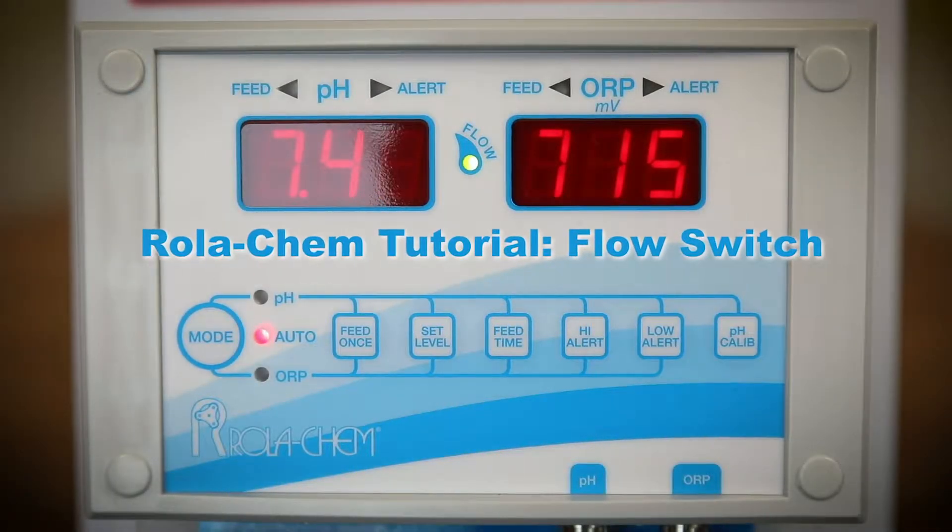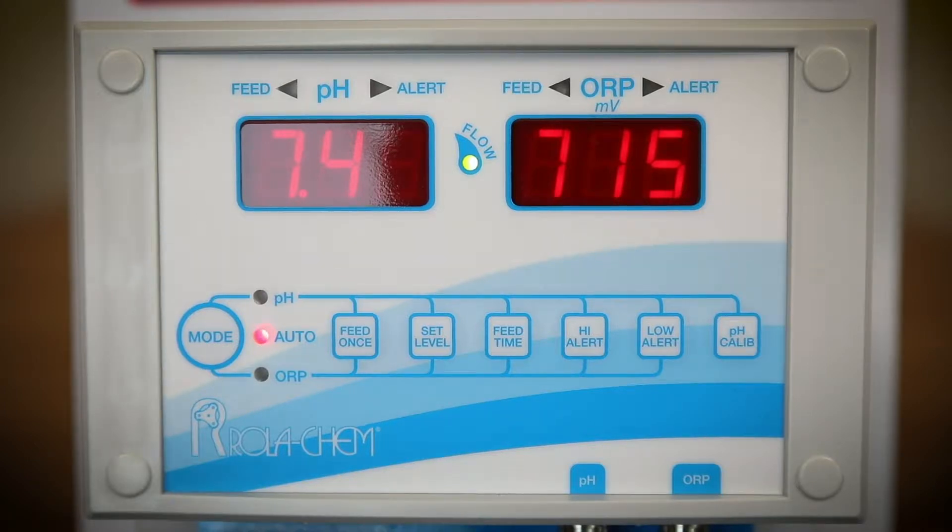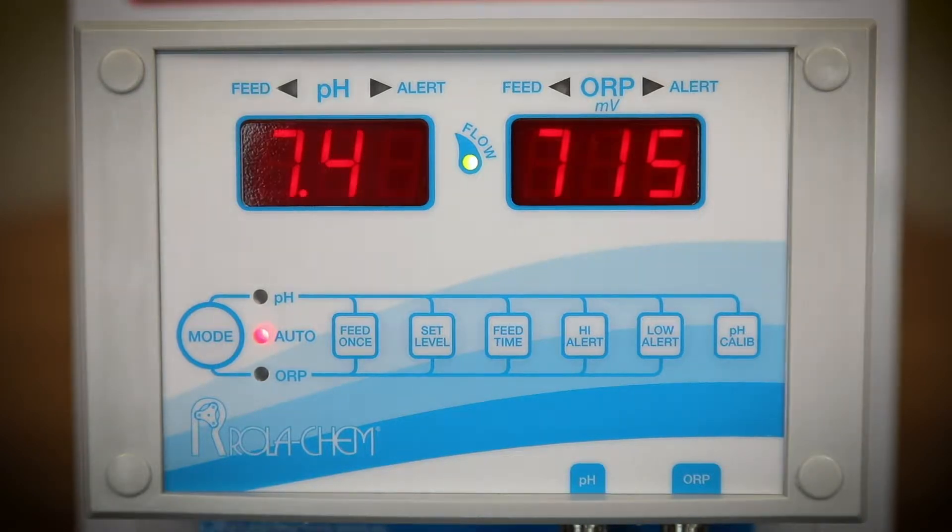In this segment we will discuss the flow switch for the 554 series Rola-Chem controller. It is important to test the flow switch periodically to ensure that it is functioning properly. A functional flow switch will disable the controller from dispensing chemical when there is no flow through the flow cell.